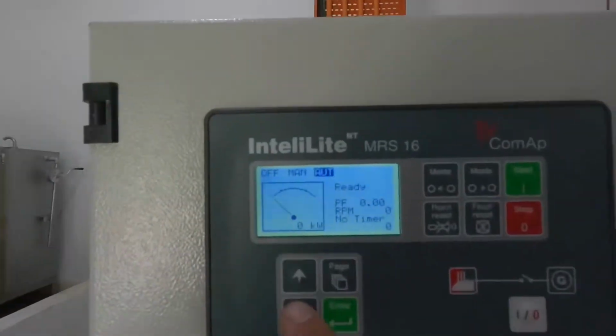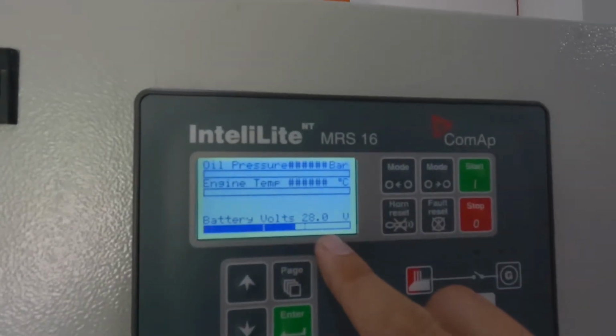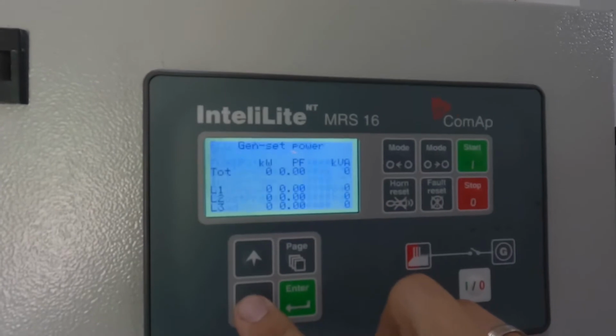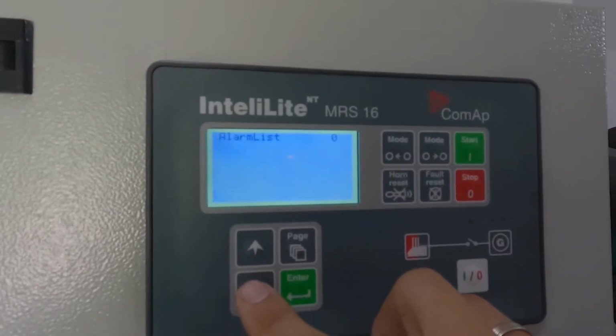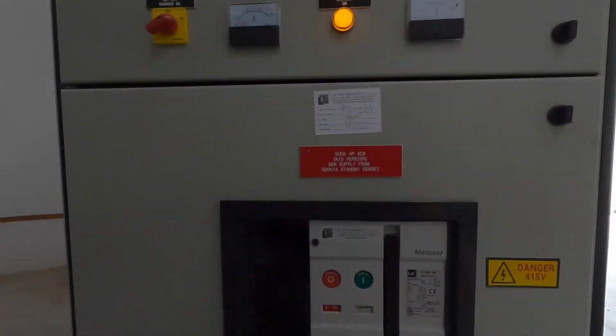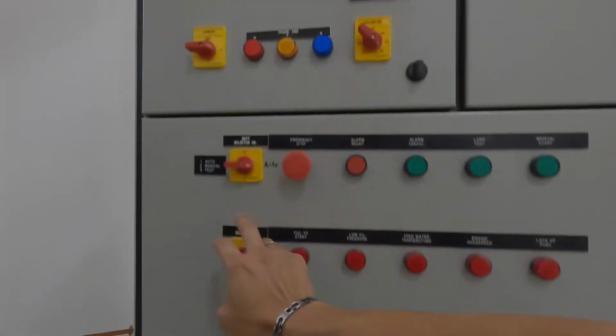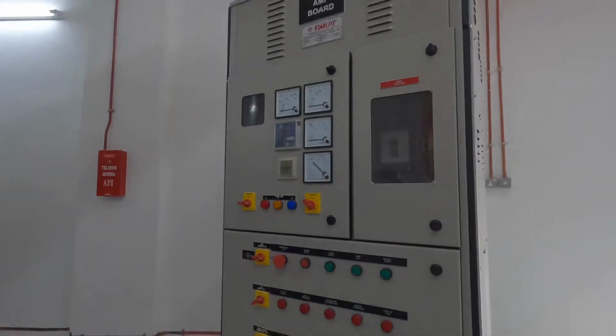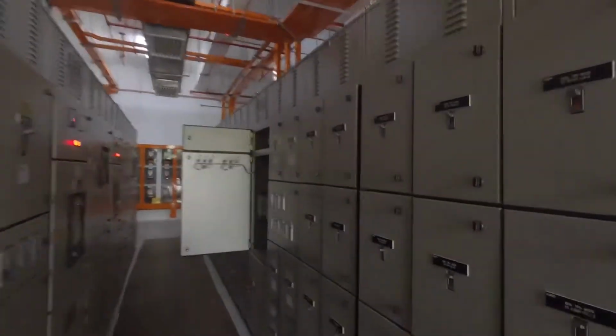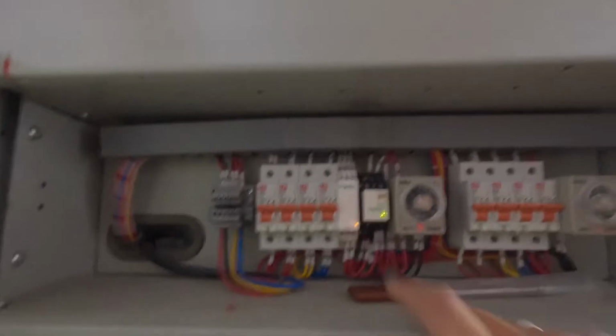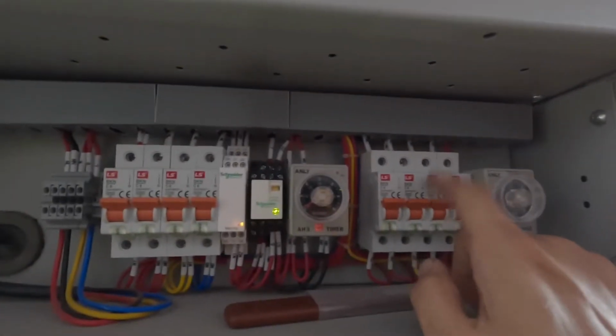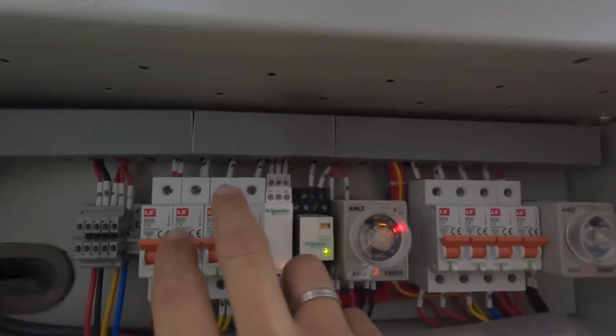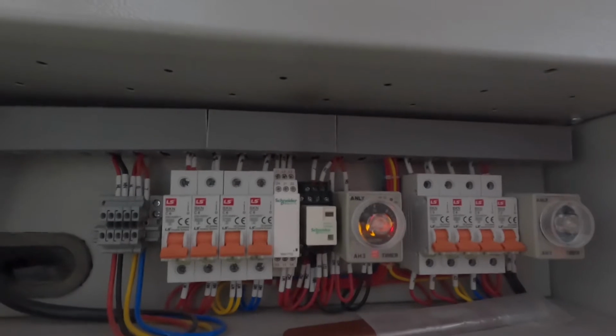Okay, here we have the controller. Battery voltage now is 28 volt DC. Okay, the AMF panel is here. ACB on, trickle charge, under auto mode. Okay, now I'm going to trigger the genset to start automatically and allow it to stop automatically. I just activate the UVR relay. Okay, here this is the UVR relay. So this is the genset supply MCB, and this is the TNB main supply MCB. So I just off the genset first, and then I off here to trigger the UVR relay, and then we wait for the genset to start.